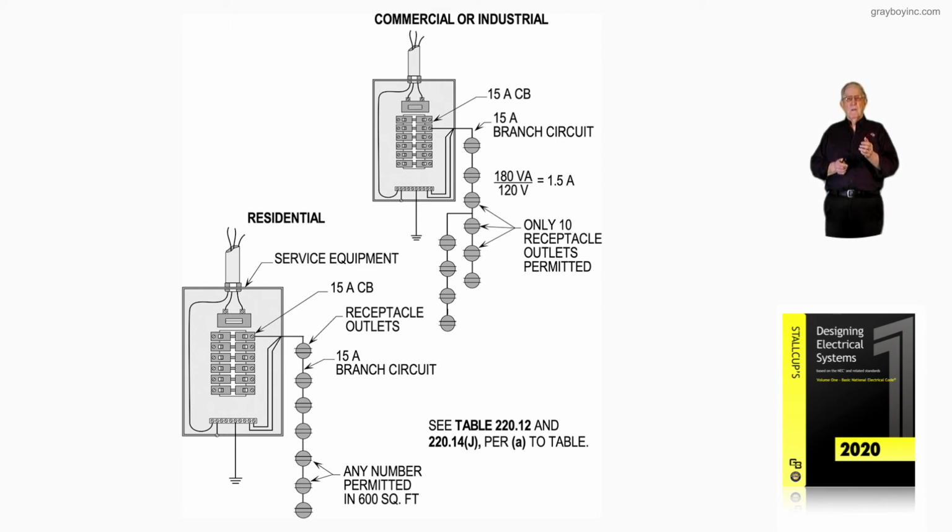You're going to use them. But if it happened to be that those receptacles were used continuous, then 1.5 is usually multiplied by 125%, and you take 2.25 into, say, a 20 amp circuit, and you'd be allowed 13 outlets. So in commercial, it's based upon continuous use or non-continuous use, general purpose circuits, meaning either way, you could have 2 or more outlets on a circuit, but how are those outlets being used?